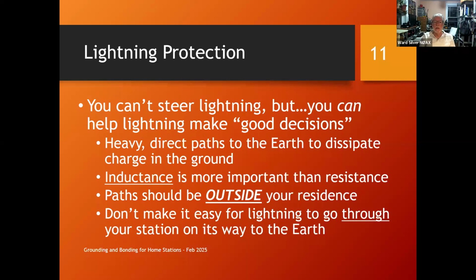So the important thing is, if you want a strong bonding connection, you want the minimum amount of inductance, because the voltage across any conductor is the inductance times the rate of change of current. The higher the frequency, the higher the rate of change of current. Think of it as L, the inductance, times delta I, the change in current, divided by delta T, the change in time. A sharp, short pulse has a very high delta I over delta T, and it doesn't take much inductance to cause a significant voltage.